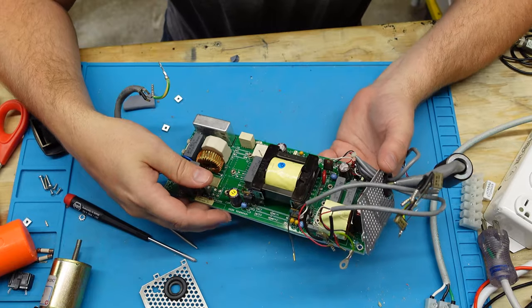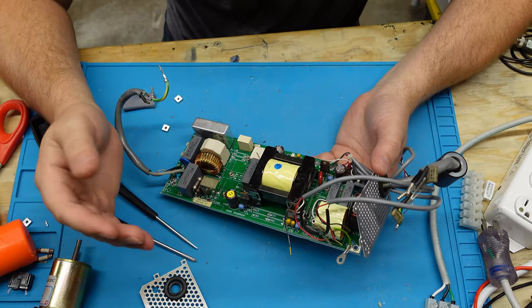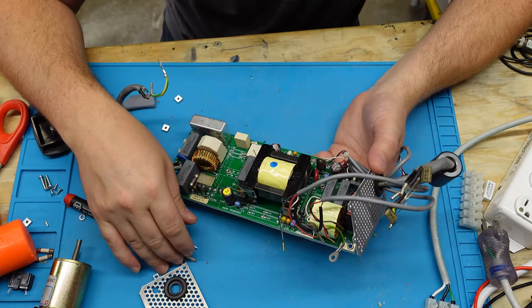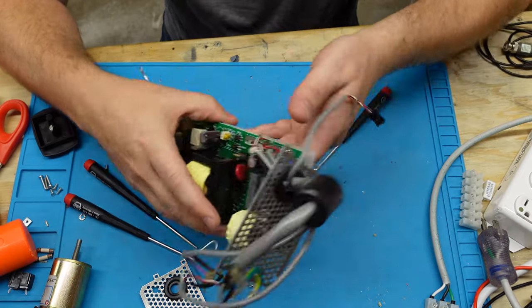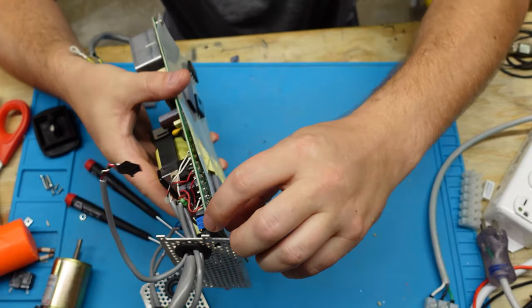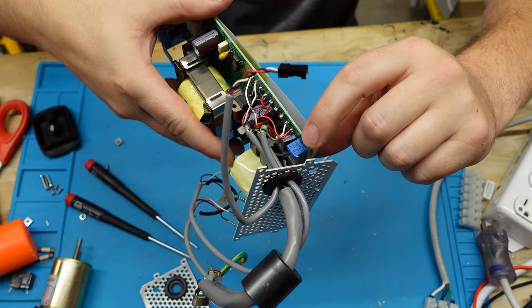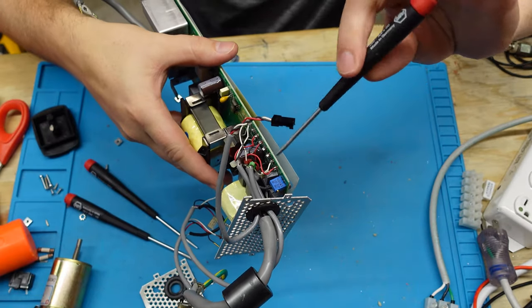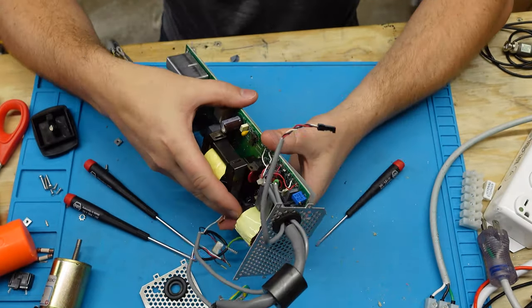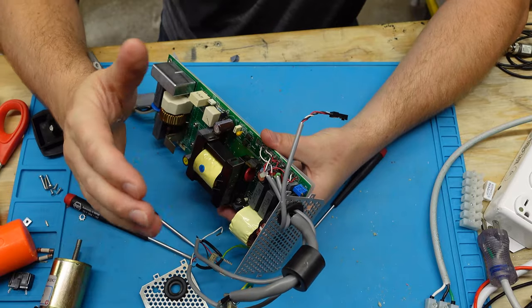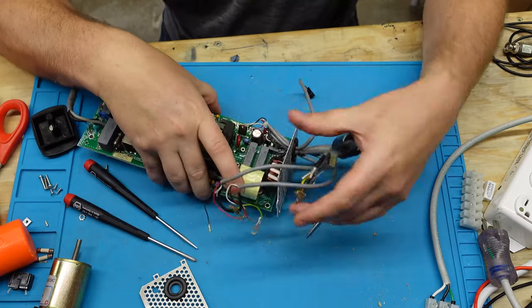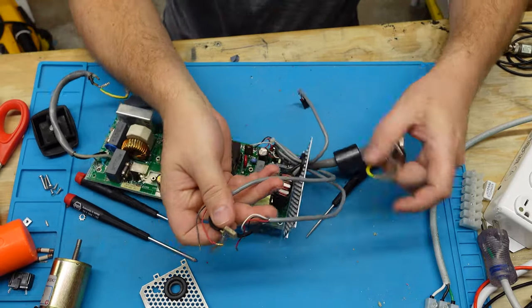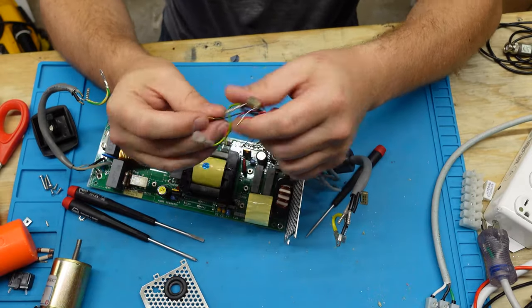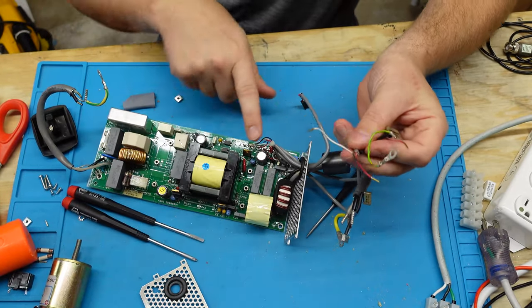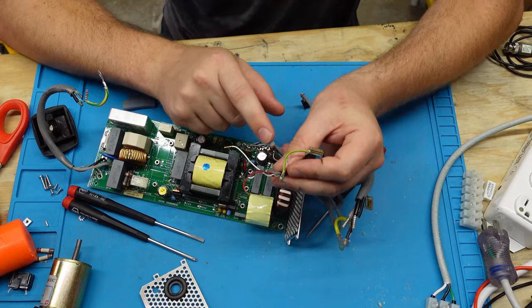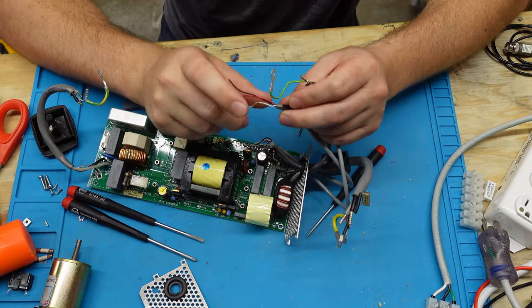And it doesn't smell like brown sugar, because that's a dead giveaway that you got a bad transformer or something. But right over here, right here in the corner, you can see that there's a little potentiometer right there. And that adjusts your calibration value for the board. So the way the output side of this works is these wires right here go to your potentiometer that's on the front of the device.